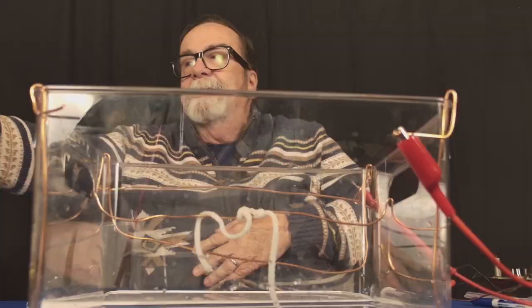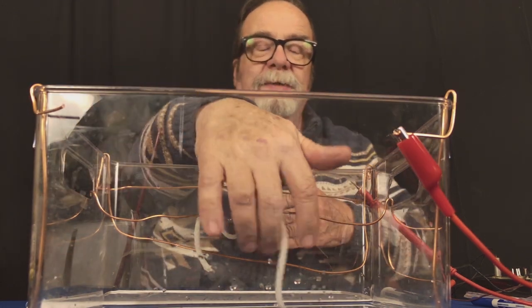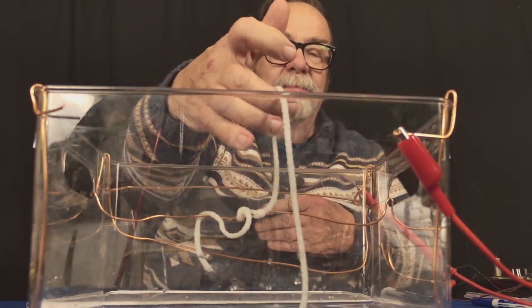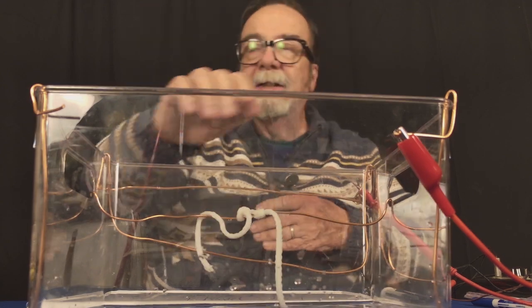Well, obviously, that was my ground fault, so I cleaned out the ants, taped up the wire, pulled off the seal tight, put a new piece of seal tight in, sealed everything back up, ground is gone. So that's one instance. Now, in relation to this tank, and pretending that this is the cable and it's underwater in conduit, another instance, and again, I was not the first one there.